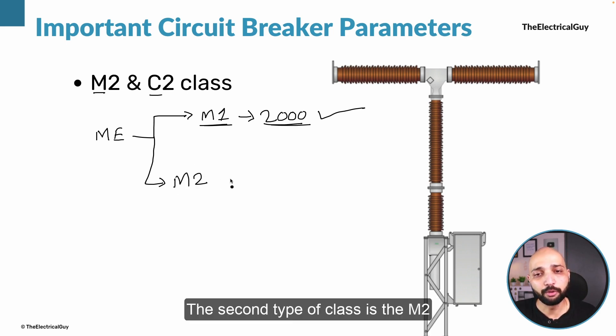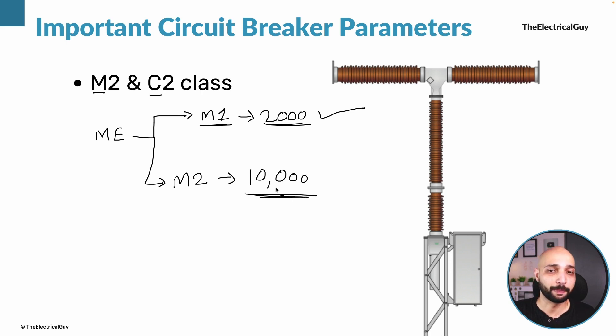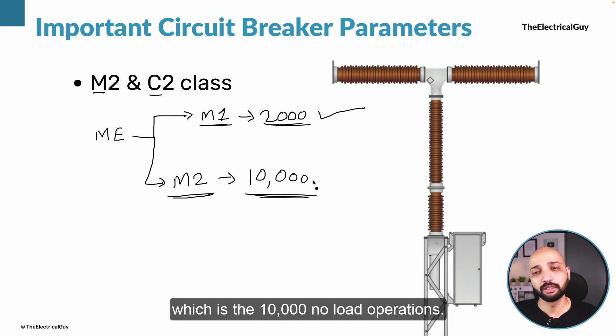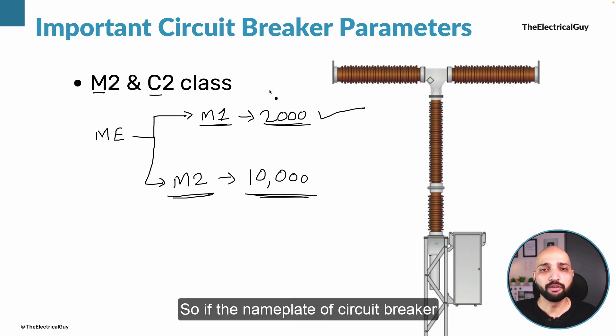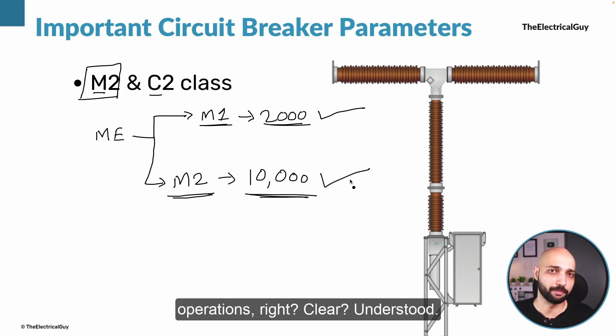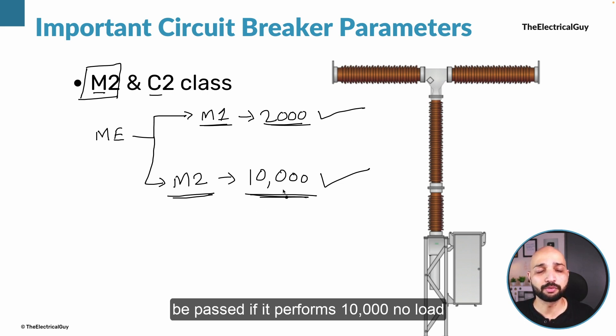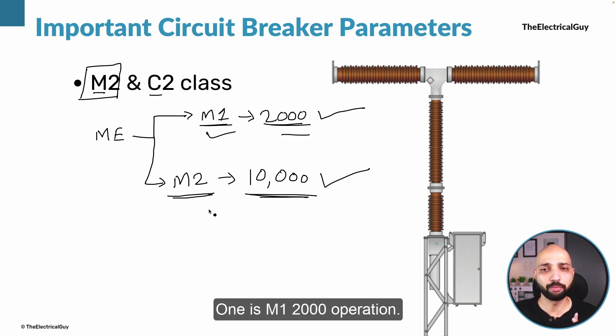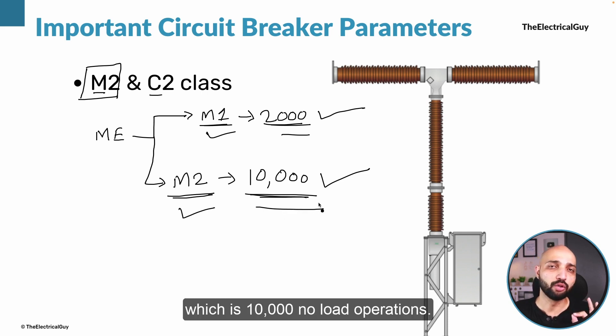The second type is the M2 class, which means the circuit breaker needs to perform 10,000 no-load operations. This is called the extended mechanical endurance class. The circuit breaker needs to perform those operations without needing any major maintenance. So if the nameplate indicates M2, the breaker has performed 10,000 no-load operations. M2 is more stringent than M1 class.